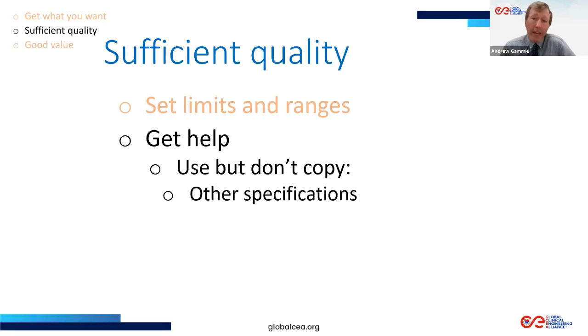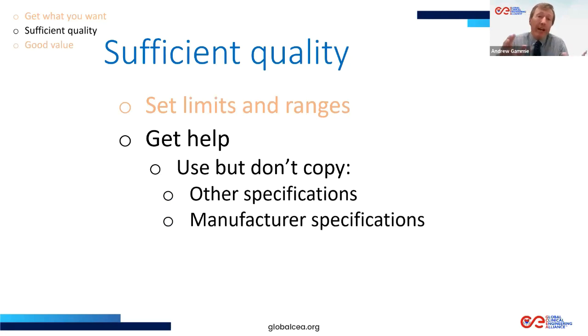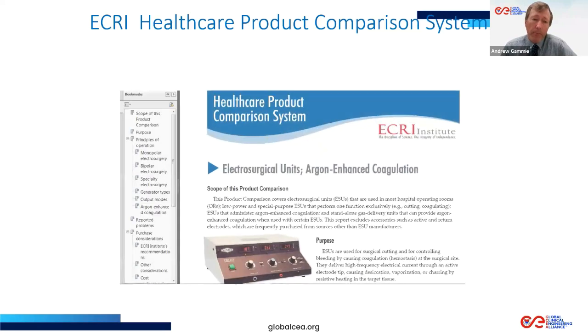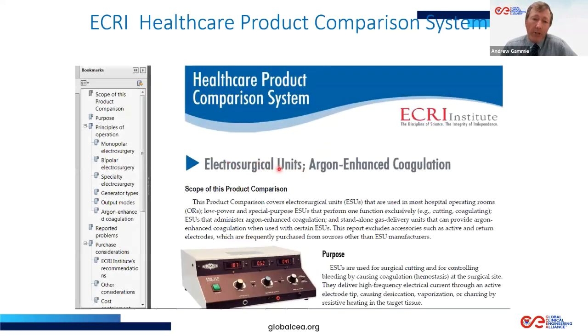The other specifications I'm thinking of are ones that have been used in your country already, or maybe you can find one online. You can also check manufacturer specifications and make sure that you're including the devices that are on the market, and make sure that you've got enough devices that fit your specification. There's another group called ECRI that can help you in this as well, although it is a subscription service, so you may not all have access to this. They run something called the Healthcare Product Comparison System, and they'll go through a lot of different devices, this one, the electrosurgical units, and talk about the different facets of the device and how it works.